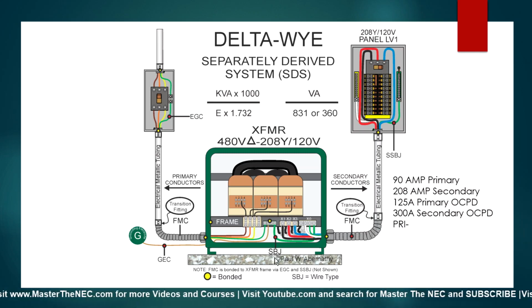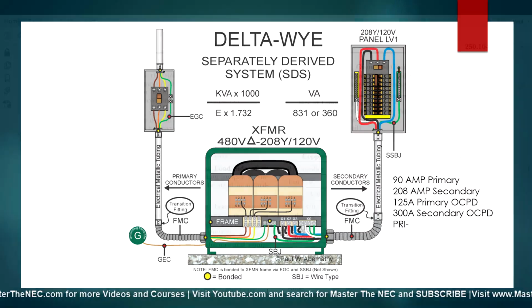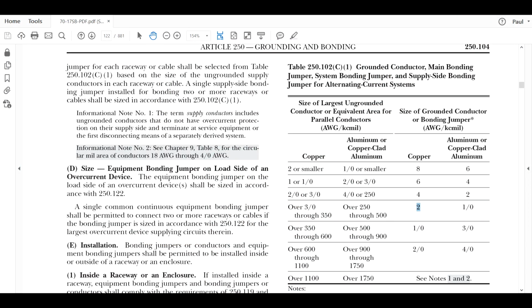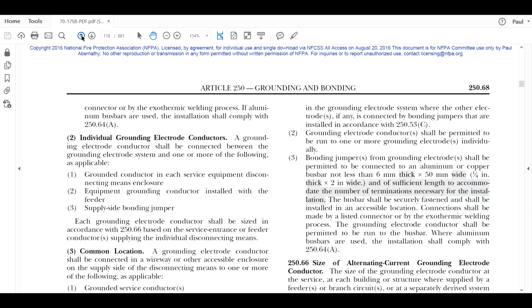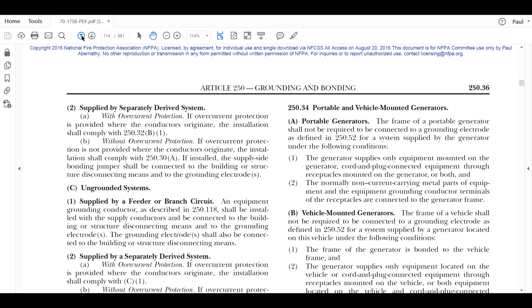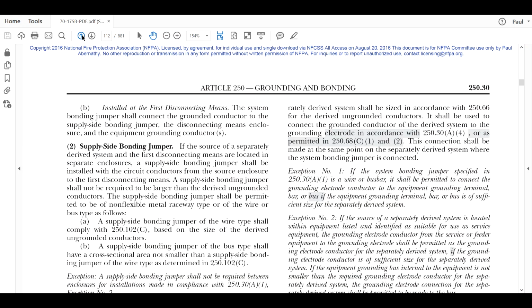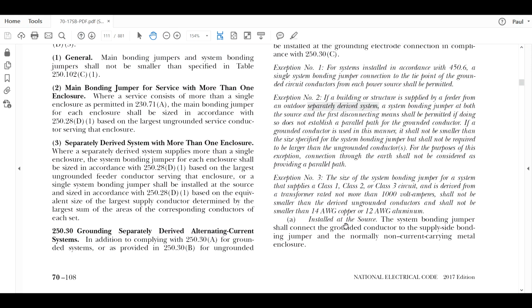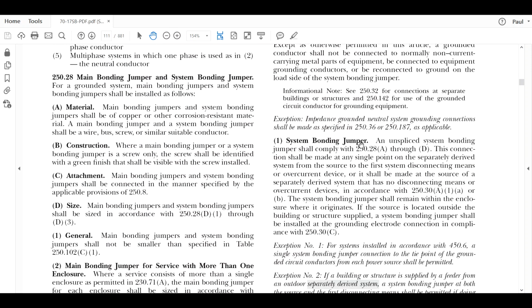So we did that. So let's do this SBJ. Let's go back to the code, and we're again going to go back to our familiar area in the code that we said to remember, and that's 250.30. We're getting all our guidance from there. So when we go to 250.30(A)(1), it says how to size that system bonding jumper, SBJ. It says the unspliced system bonding jumper shall comply with 250.28(A) through (D).